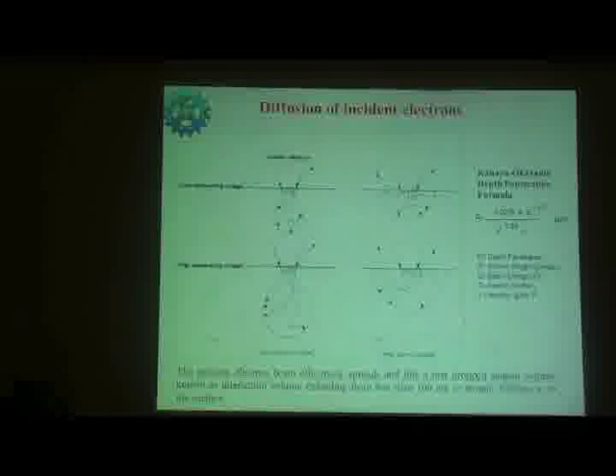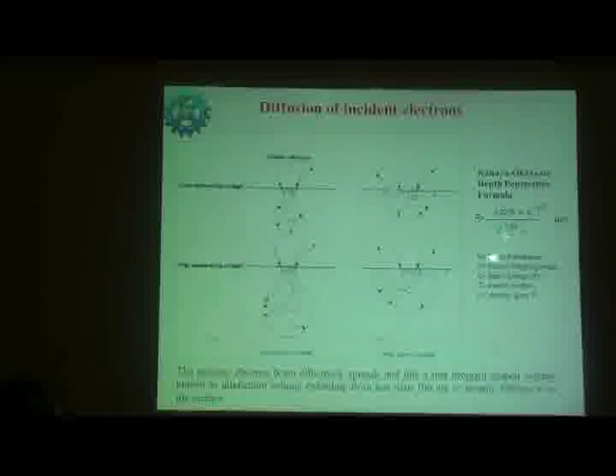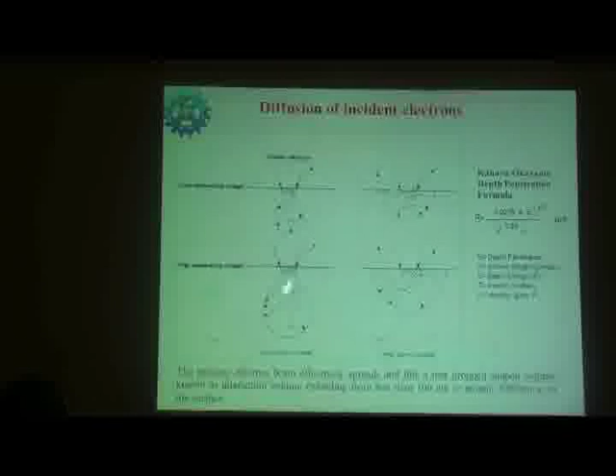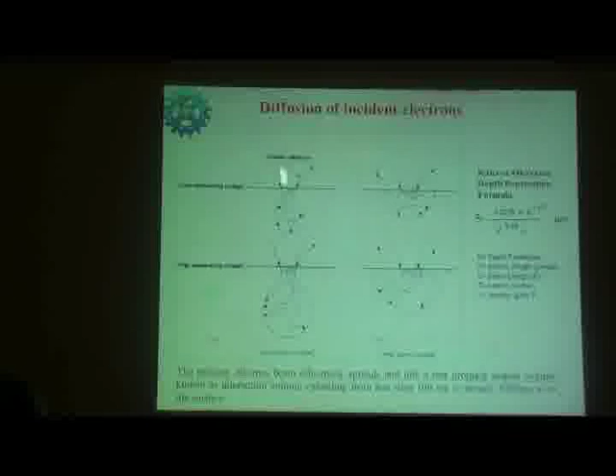The depth of penetration depends on many factors. One is the accelerating voltage, that is the energy of the beam. The other is the atomic number. Suppose the same sample can be done with different accelerating voltages, a low accelerating voltage and a high accelerating voltage. With a low accelerating voltage, this is the interaction volume. The interaction volume increases with a high accelerating voltage, meaning you have used a very high energy beam.